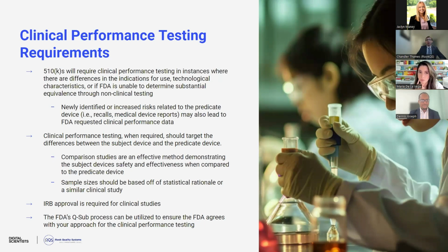So this process can be streamlined using the FDA's Q-Sub process to ensure that FDA agrees with your approach for the clinical performance testing. With clinical performance testing being so expensive and so timely, definitely recommend going through that Q-Sub process to make sure that FDA agrees with your approach. Otherwise, you run the risk of performing an expensive and timely clinical study, including that in your regulatory submission, and then the FDA comes back and for whatever reason doesn't agree with your study or has an issue with the end results or the data within that study, and you have to repeat any sort of clinical testing or do another study to fully bridge that gap with FDA. So going through that Q-Sub process is really a risk mitigation tool to make sure that you don't lose any more time or money as part of this process.